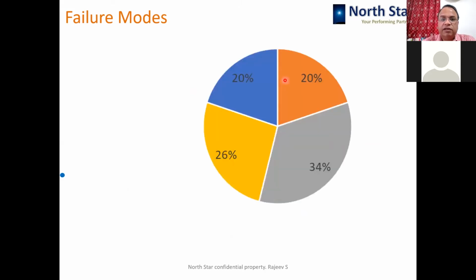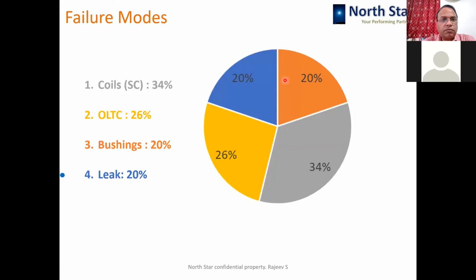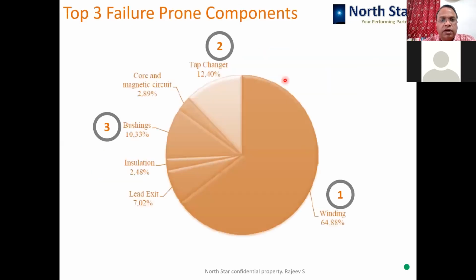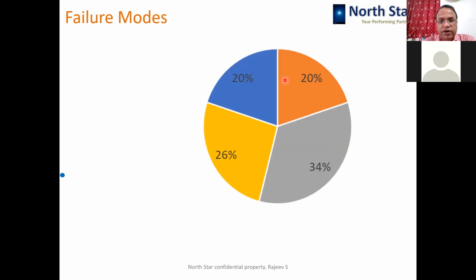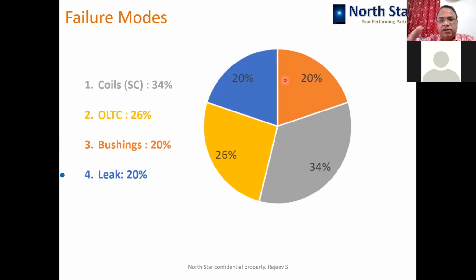So if you look at why the bushing fails, yeah, these are the three categories. And if you look at failure modes, there is another data over here where coils are failing, 34% with short circuit happening. Then bushing failure here is 20%, OLTC is 26%, and leak again 20%. So if you see here, the sequence is almost the same, and further leak is also added over here. That leakage also causes the transformers to fail. In 20% of total transformer failures, it happened because of leakages.